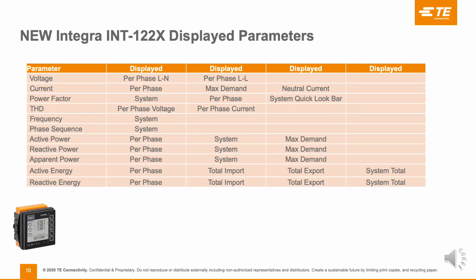Okay, to the parameters, what are displayed actually on the 4-line display. As you can see, the voltage will have phase to neutral and phase to phase on there. The current will have the phase again, line 1, line 2, 3, also maximum demand, and also it will display a calculated neutral current. Power factor, it does a system power factor, it also does power factor per phase, and as mentioned on the previous slide, it has got a quick look bar, so you can see if you are near unity power factor. Harmonic distortion, it has on there per phase on the voltage and per phase on current. Does the system frequency, and also offers the additional facility of phase sequence, so you can check if your voltage and your current are in correct phase sequence.